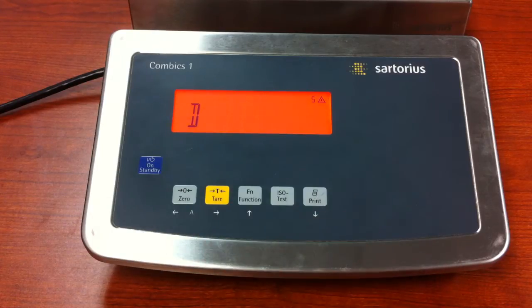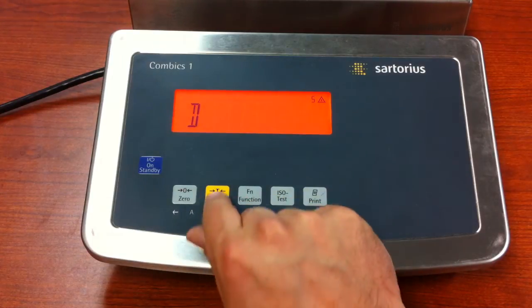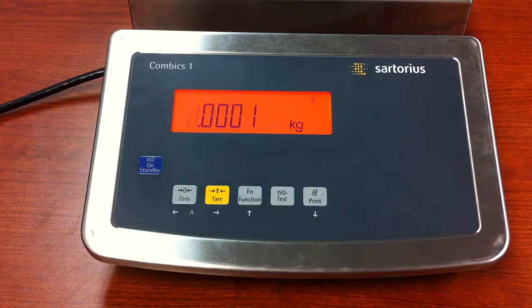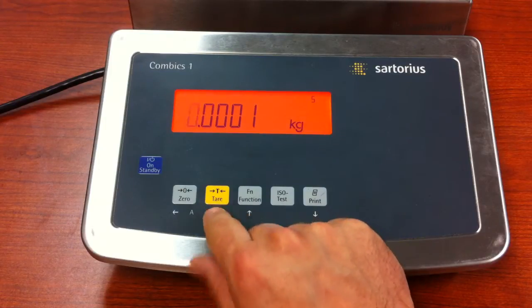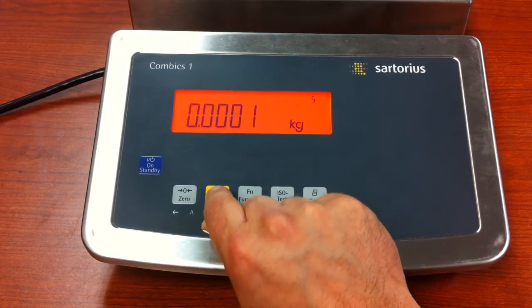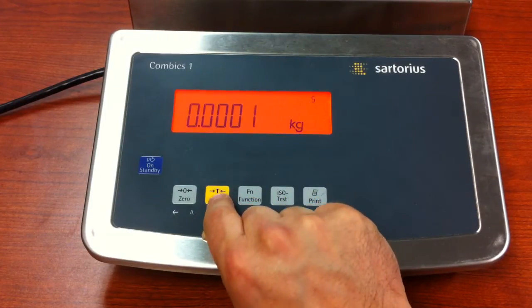The next step will be setting up your grad size, otherwise known as D. Press and release the tare key and now you can set up your resolution. Right now we have it set to 0.0001 kg, and that works just fine for me, so we're going to press and release the tare key.